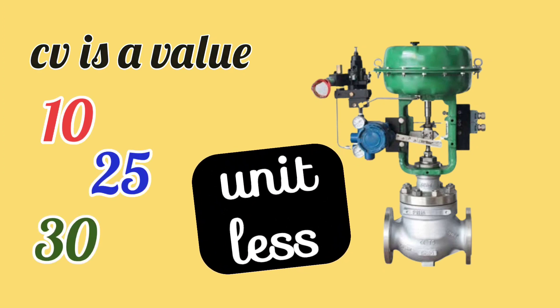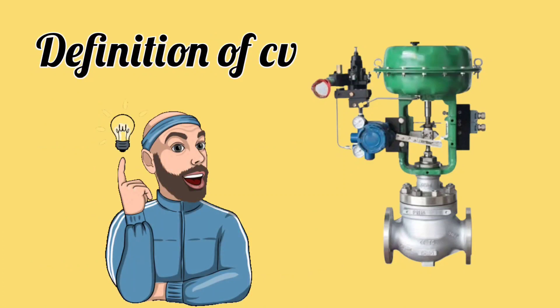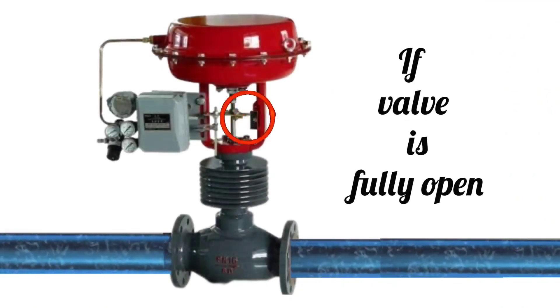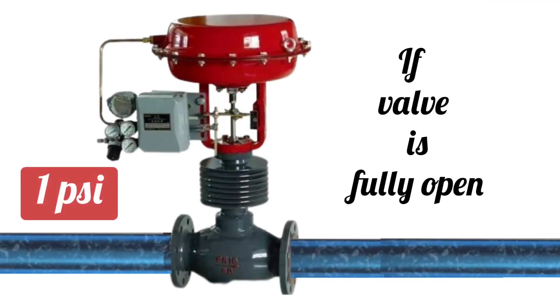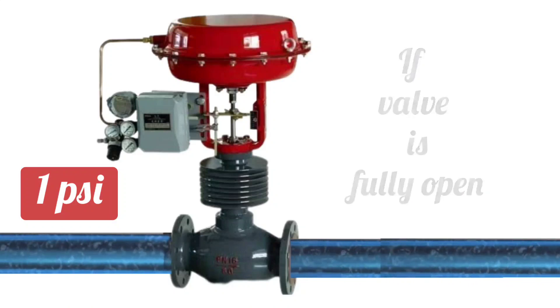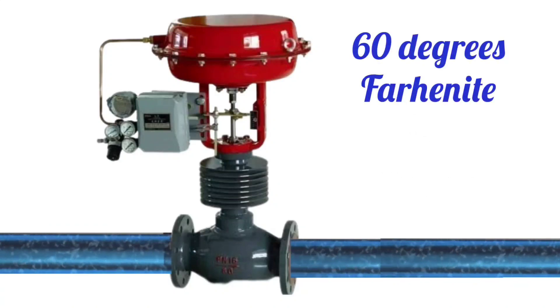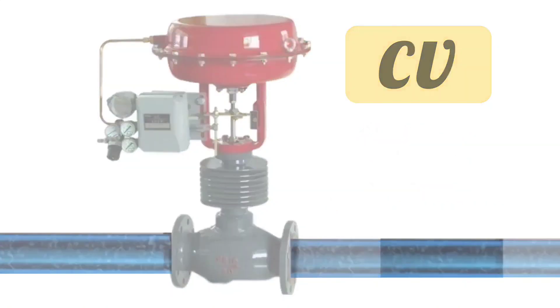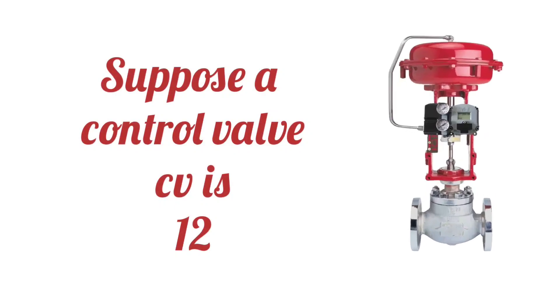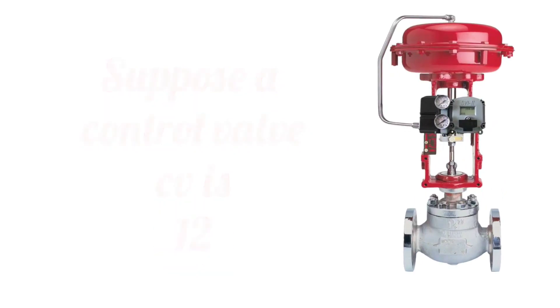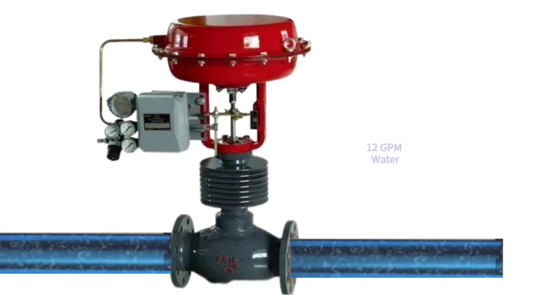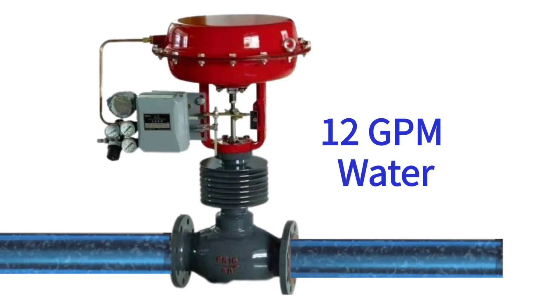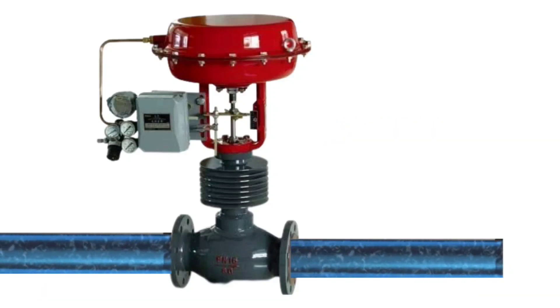If we see the definition of CV: when the valve is fully opened and there is a pressure drop of 1 psi, then at 60 degrees Fahrenheit, the gallons per minute of water flow is called CV. For example, if the CV of a control valve is 12, then in fully open condition the valve will pass 12 GPM of water, when there is a pressure drop of 1 psi and the temperature is 60 degrees Fahrenheit.